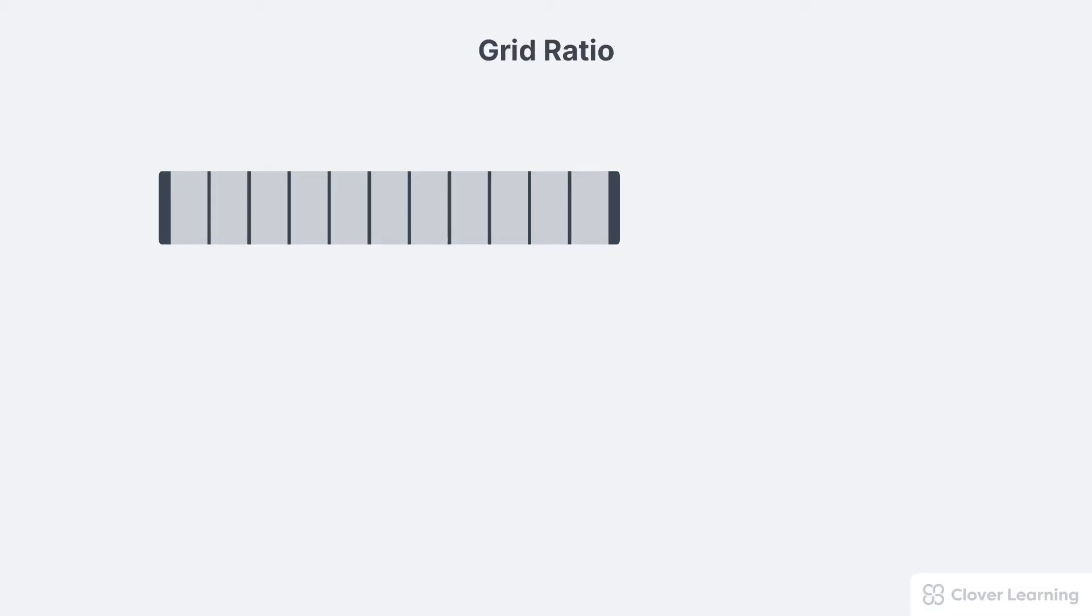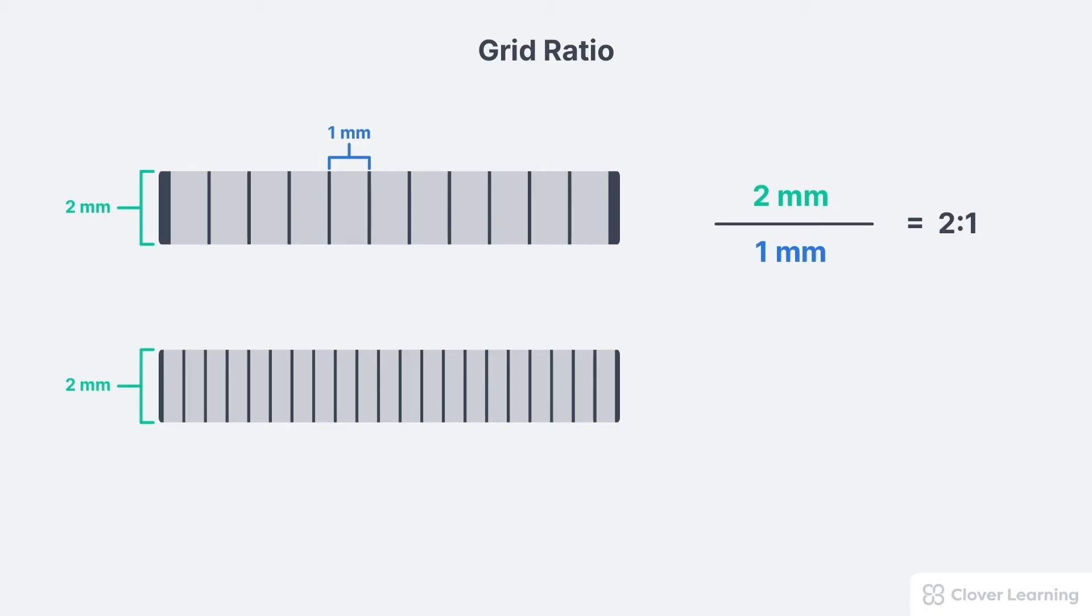The efficiency of a grid in removing scatter is designated by its grid ratio. The grid ratio is defined as the height of the lead strip compared to the distance between them. For example, a grid having lead strips two millimeters high and having one millimeter of distance between each strip has a grid ratio of 2 divided by 1, which is 2 to 1. If the distance between the strips decreases to 0.5 millimeters, then the new grid ratio is 2 divided by 0.5, which is the same as 4 to 1.